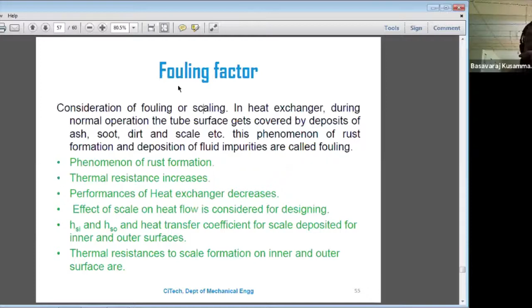If they ask you to write a short note on the fouling factor, you have to write like this. Anyhow, the formula is given in the data handbook, so you can note it from there. First of all, write these things about the fouling factor. Then write how to calculate the overall heat transfer coefficient if you consider the fouling factor, representing the two formulas based on the inner and outer surfaces. Then the reciprocal of that is the scale heat transfer coefficient Hs, which is called the fouling factor. You should know these things. So this is regarding the fouling factor.